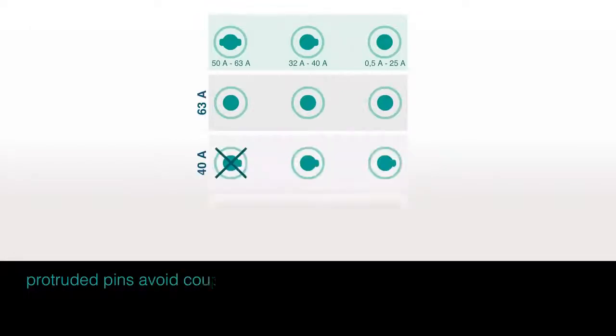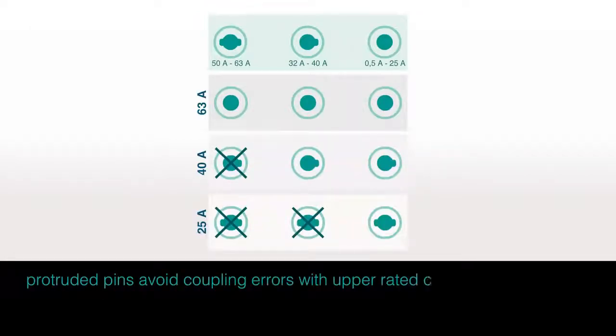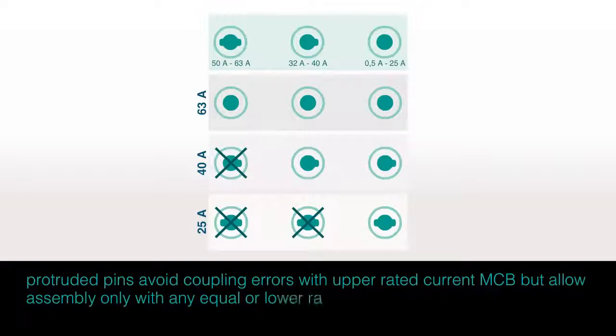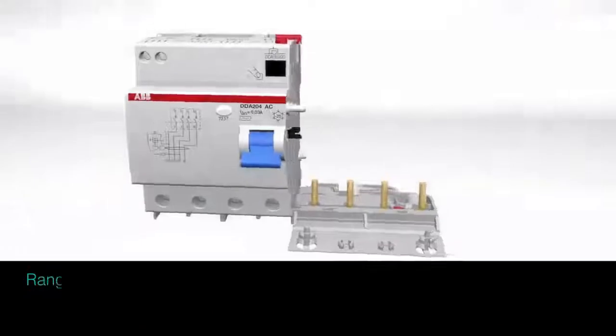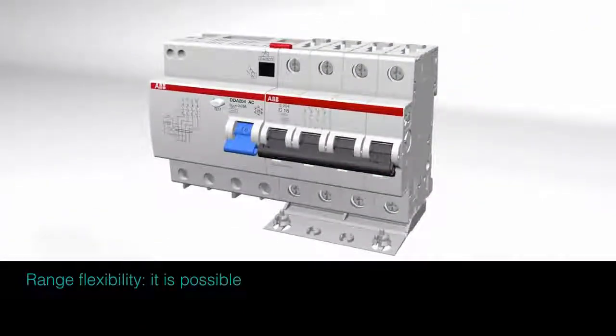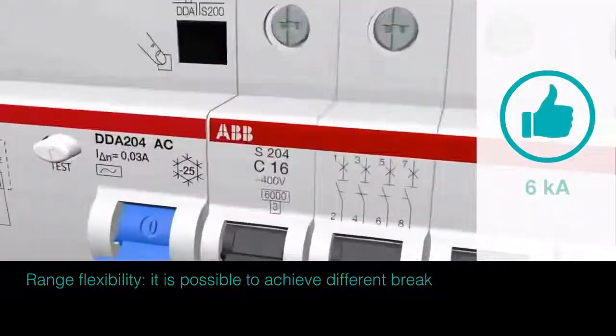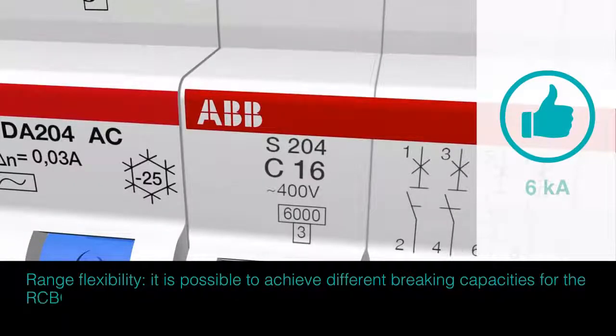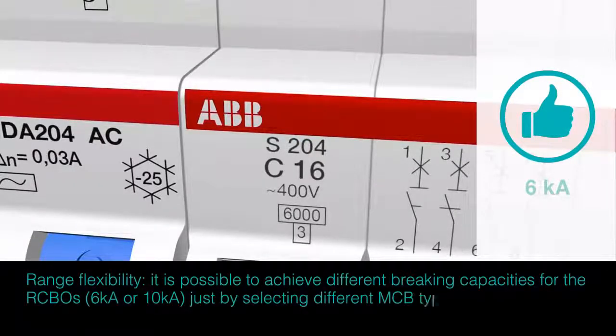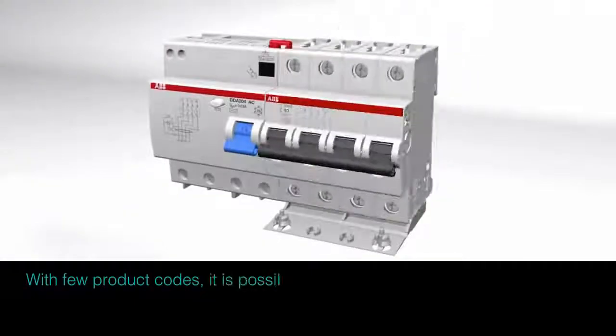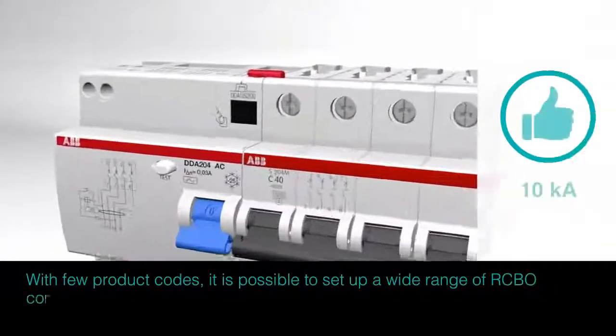Protruded pins avoid coupling errors with upper rated current MCB, but allow assembly only with any equal or lower rated current MCB. Range flexibility. It is possible to achieve different breaking capacities for the RCBOs, 6 kA or 10 kA, just by selecting different MCB types, S200 or S200M. With few product codes, it is possible to set up a wide range of RCBO combinations.